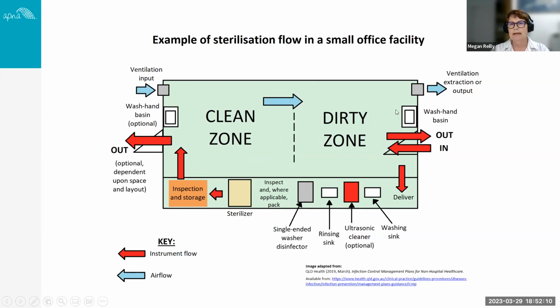In our dirty zone, we can see that we have receipt of our instruments. We have our sinks. We've got 2 sinks here, our washing sink, an optional ultrasonic cleaner in the middle, then followed by our rinsing sink. And then this is just a single either underbench or benchtop washer disinfector in this instance. And then we tend to have this neutral area here. So we're actually now moving from the dirty zone into the clean zone, where we're inspecting and packaging our instruments, if that's indicated. We're now in the clean zone, and then we move forward into our sterilizer, to our inspection and our storage area, and then out the optional door there. So you can see that we are getting that unidirectional flow from dirty to clean in this instance.